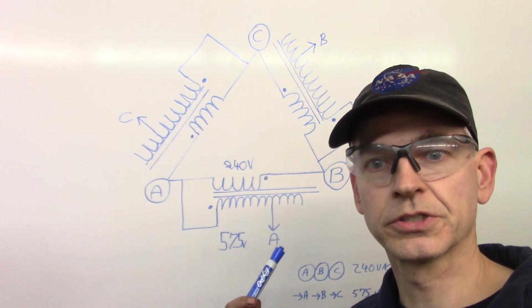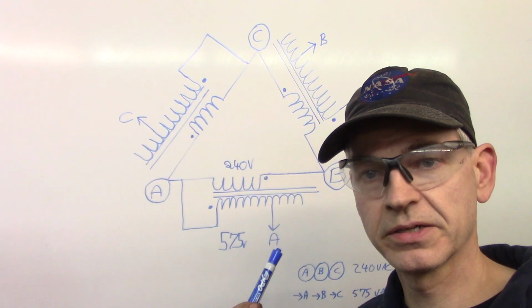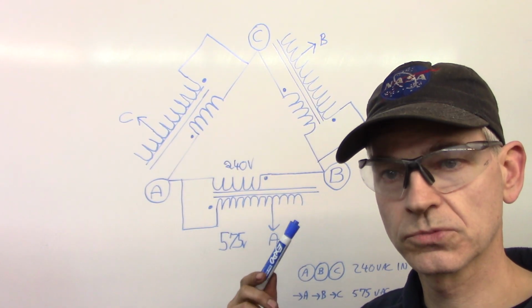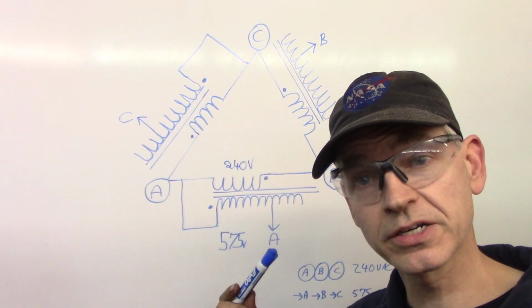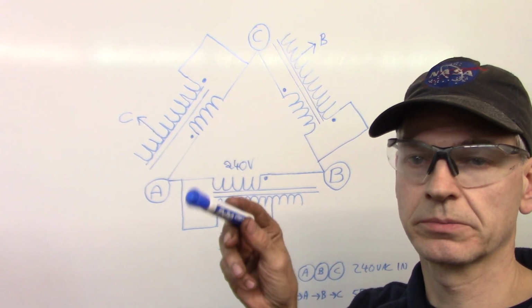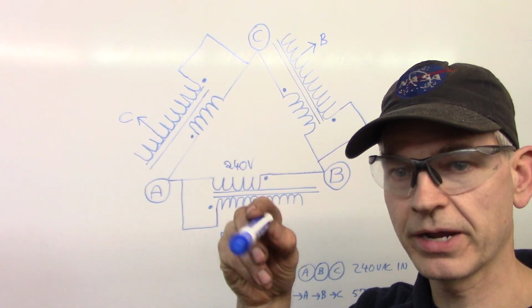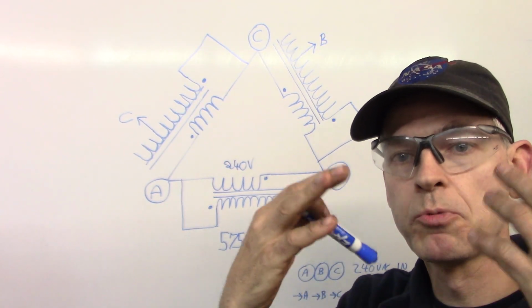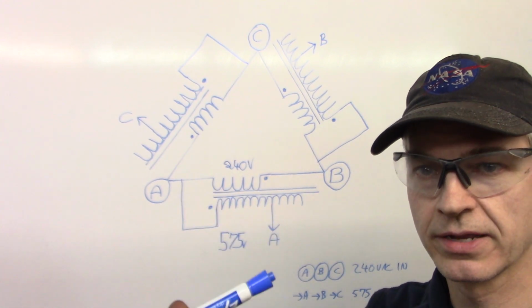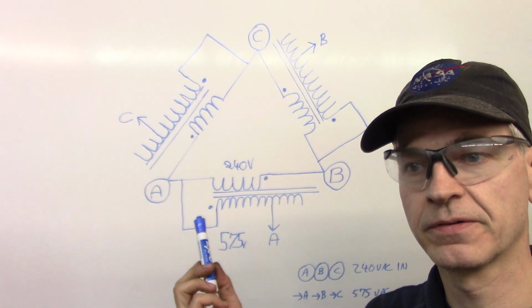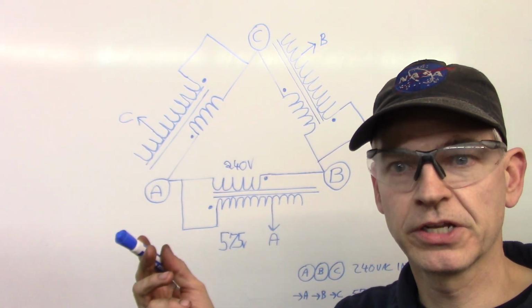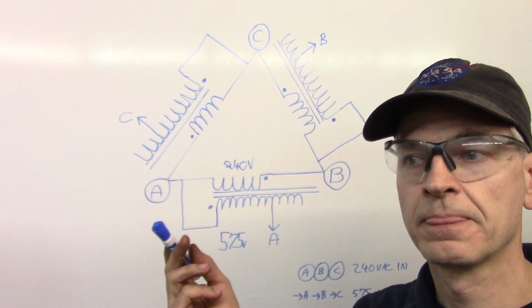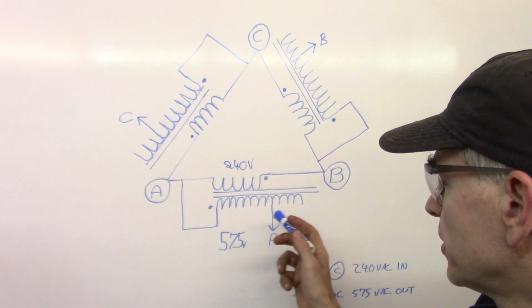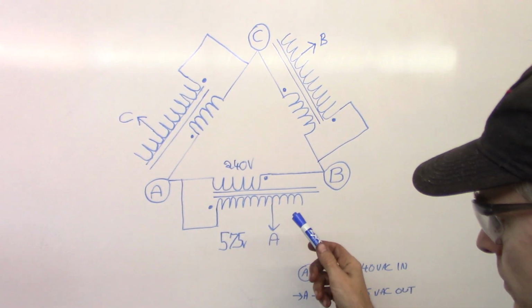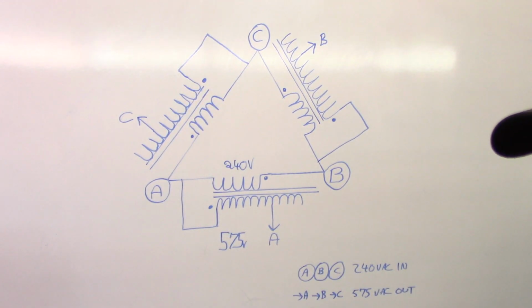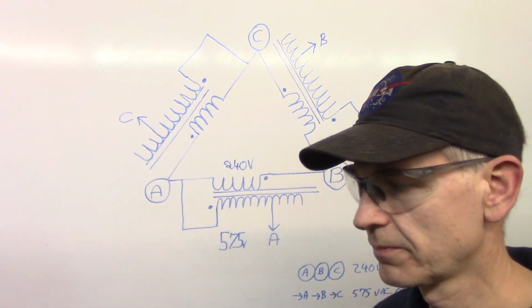I would reduce the voltage if I bucked, because that's if you change the direction of the windings. I'm keeping the direction of the windings the same - I'm just going to make this up and call it clockwise. Clockwise in the primary, clockwise in the secondary. So it's boosting, it's making the voltage boosted. So it's an auto transformer configuration running in a boosted orientation. Everything I do is going to be boosted up because my winding orientation is in the same direction. Hope that makes sense.